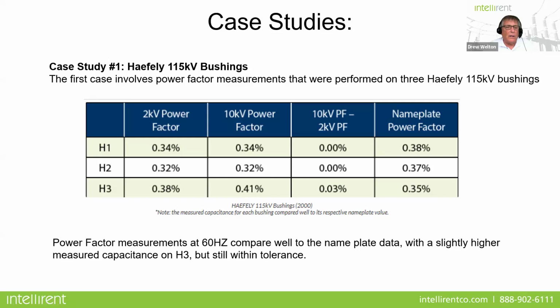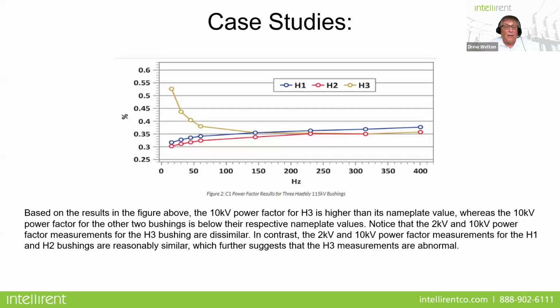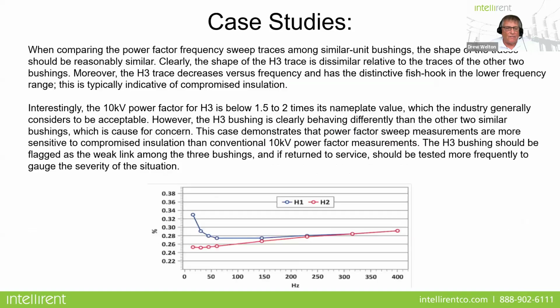Now, if we look at our variable frequency test, you can see quite clearly that the H3 bushing has a much higher power factor value in that lower range. Now, what that would tell me, if I was doing an analysis on this, is that H3 should be looked at much more carefully and probably retested at a later time, just to make sure that we're not going to have a problem. But of the three bushings, H1 and H2 look just fine. H3 is going to raise some suspicion in terms of going down the road for further maintenance testing.